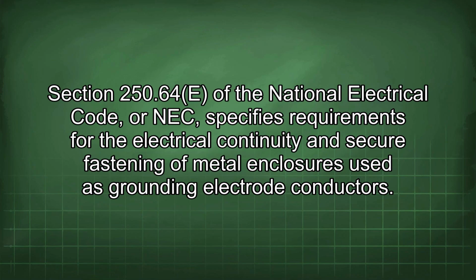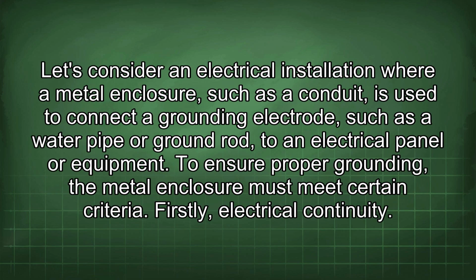250.64(E) of the National Electrical Code, or NEC, specifies requirements for the electrical continuity and secure fastening of metal enclosures used as grounding electrode conductors. Let's consider an electrical installation where a metal enclosure, such as a conduit, is used to connect a grounding electrode, such as a water pipe or ground rod, to an electrical panel or equipment. To ensure proper grounding, the metal enclosure must meet certain criteria.